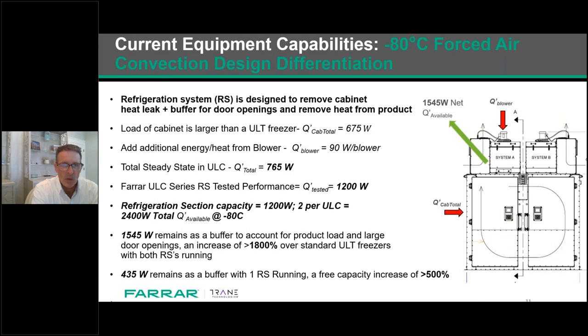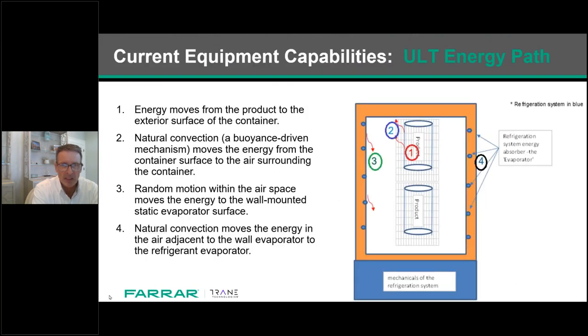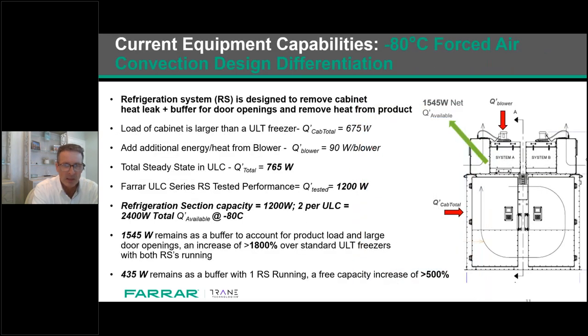So when we look at the current capability, this is on the previous slide, sorry, we're having some technical difficulty, but on this slide you see what's called a ULC, which is an ultra low freezer. It is a forced air convection refrigeration design, and it's a reach-in. Let's focus on the heat load and the ability to remove the energy. Keep in mind, this is a forced air convection refrigeration design, and it has the capacity of approximately 8 ULT freezers. The storage capacity inside is 190 cubic feet.